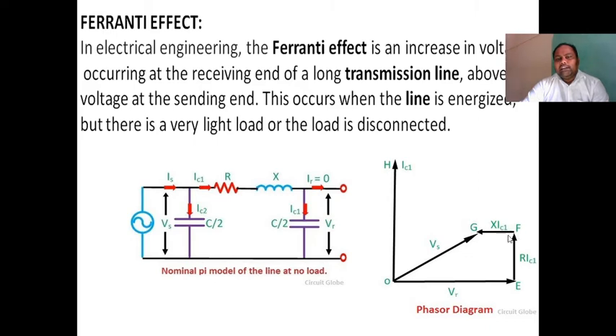Next, how do we draw IC1X? It is drawn 90 degrees from the resistive drop, since the reactive drop is 90 degrees from the resistive drop. So what is the sending end voltage? It is the vector sum of the receiving end voltage plus IC1R plus IC1X, which is nothing but VR plus IC1 times Z, where Z is the resistance and reactance. So this drop is due to the IC1 charging current only.